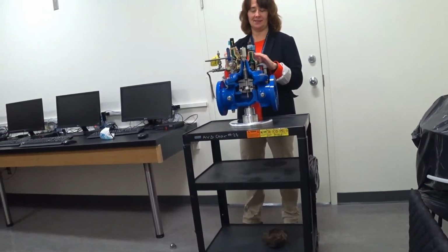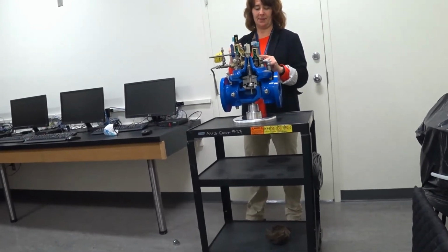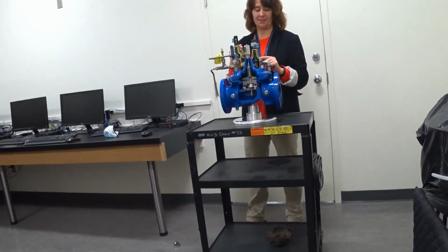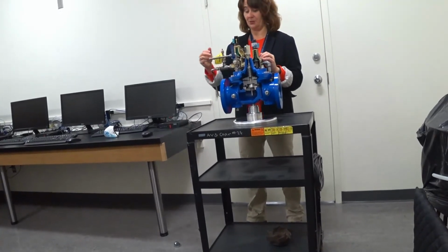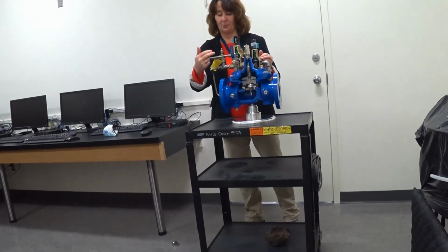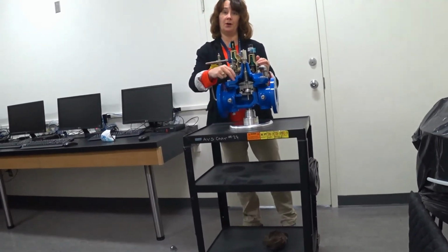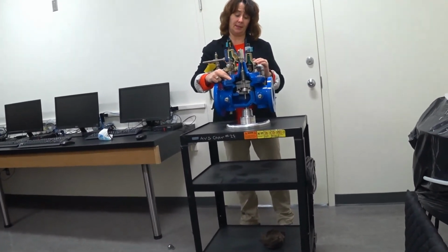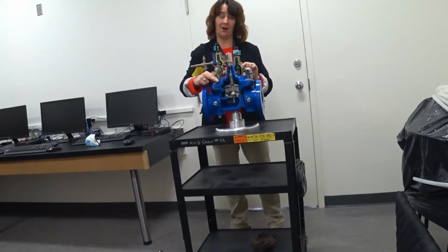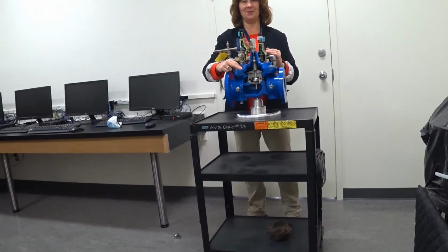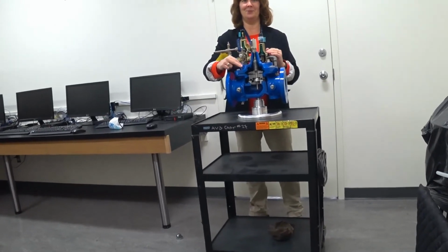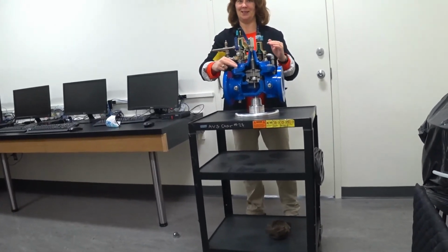That's all this guy does. It says, so I'm set at 60 psi. If I go above 60 psi, I'm going to start to close. If I start to close, the pilot water is going to be diverted onto here, which will cause the main valve to close. So basically, this pilot valve and the main valve model each other. They follow. So if this one's closing, this one's closing. This one's open, this one's open, right? So that's how they go.